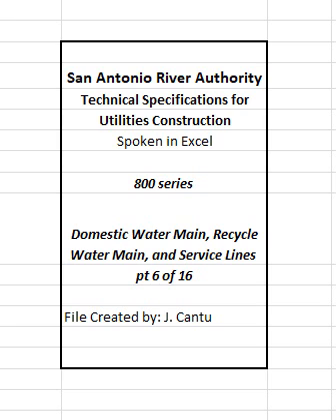For recycled water mains, the pipe shall have 3 pairs of longitudinal purple stripes, co-extruded into the pipe outside surface. Stripes printed on the outside of the pipe shall not be accepted. If purple striped pipe is not available, the pipe must be bagged in purple polyethylene plastic, 8 mil, and shall be installed per this specification.